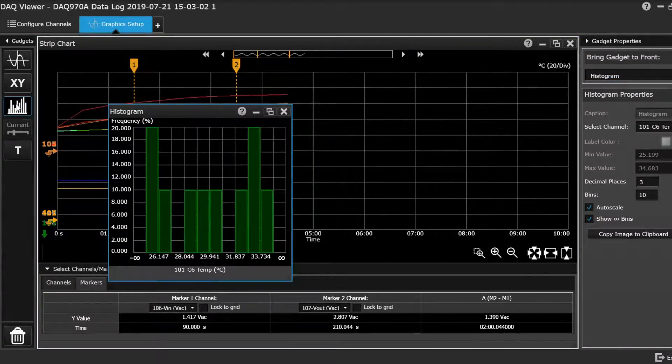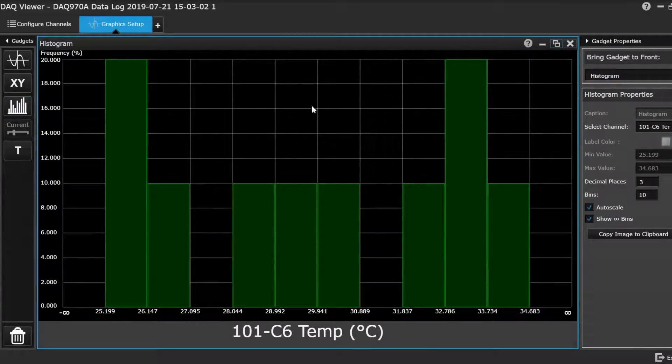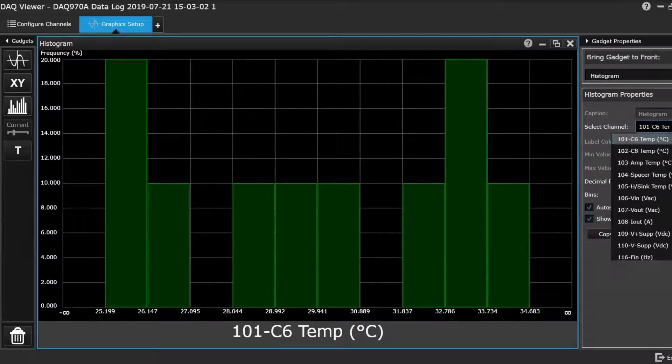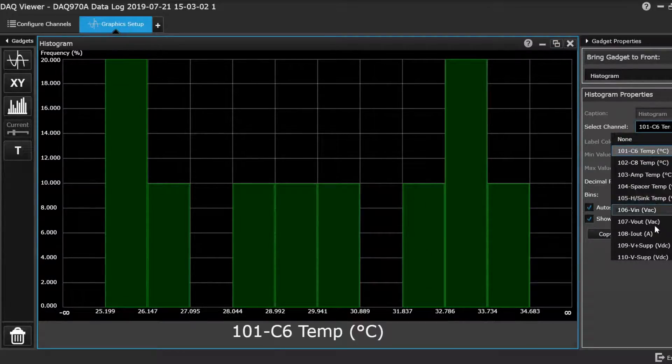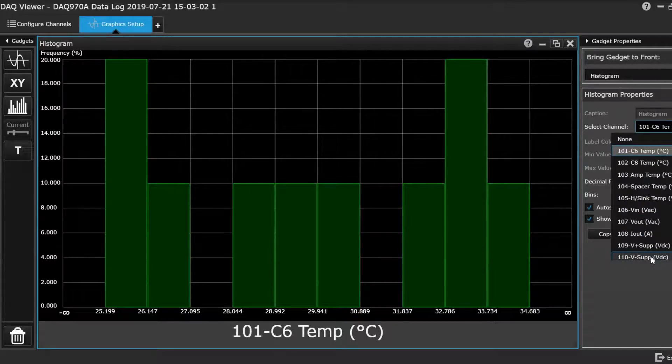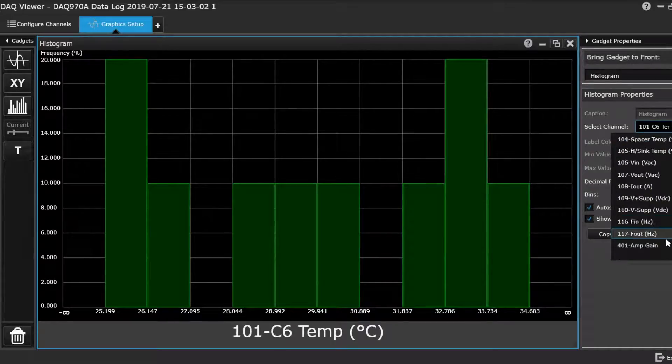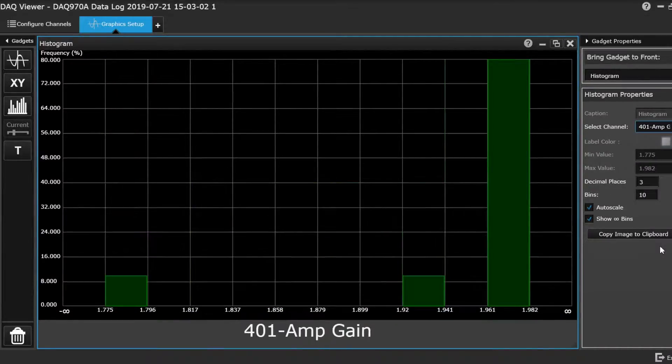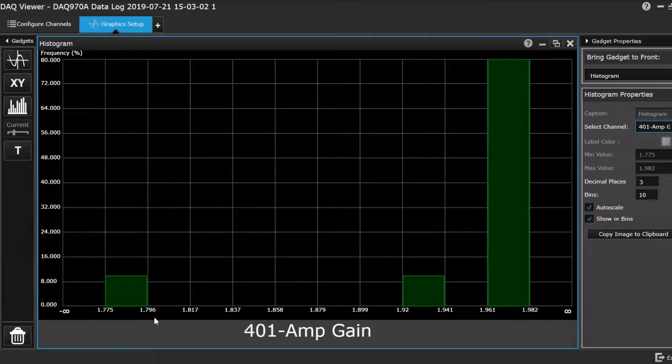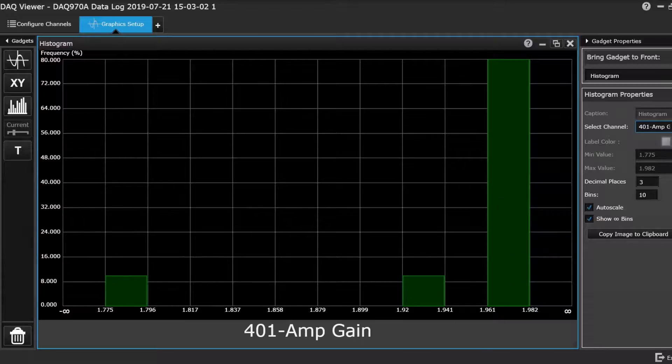And you can also have a histogram. And again, this is just a single channel selection. So let's go all the way down the bottom. Your amp gain. I can tell the amp gain floated between 1.775 and 1.982. The majority of them are 1.982. So that's another little bit of analysis you can do as well.